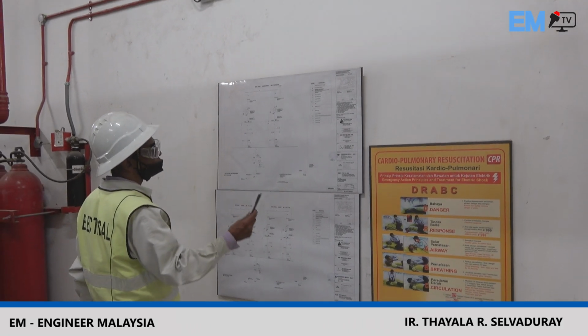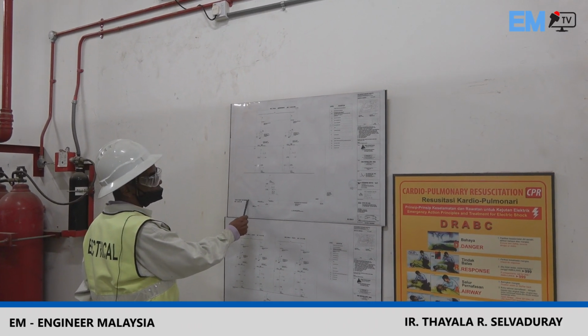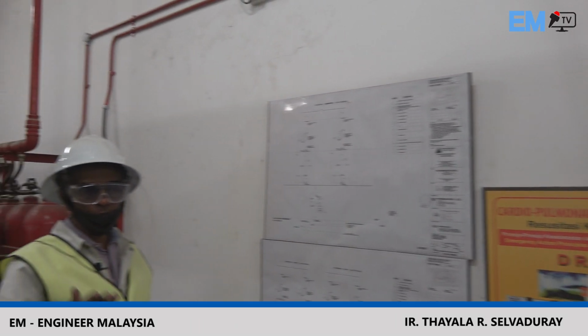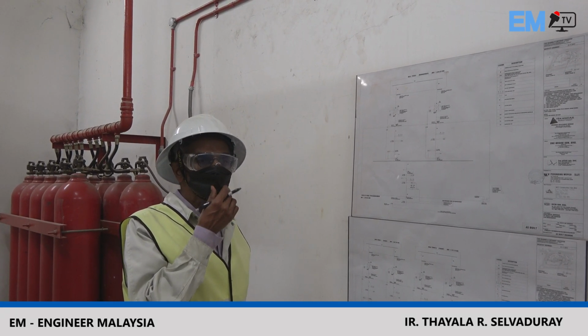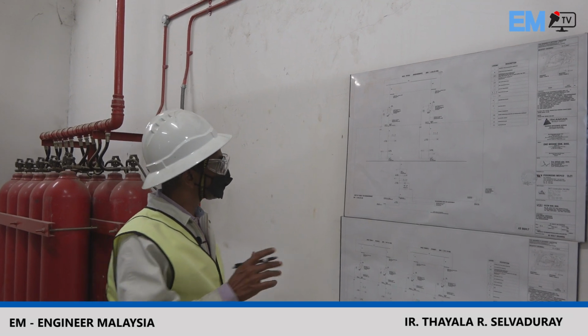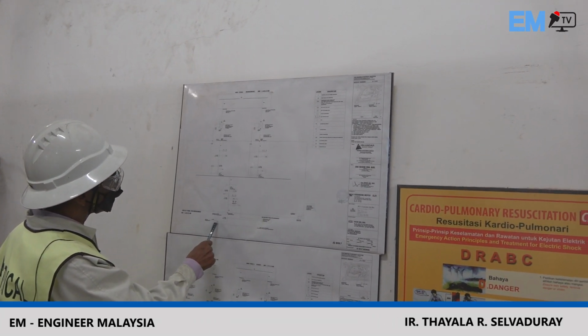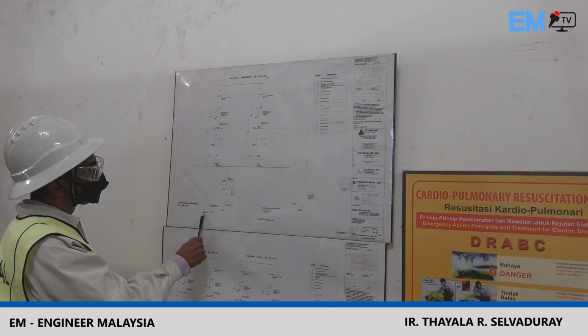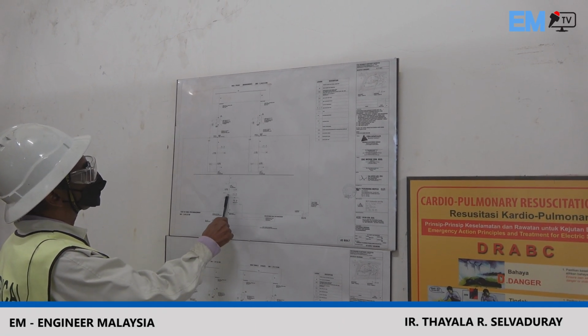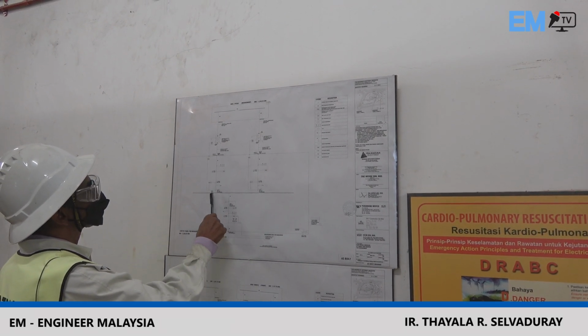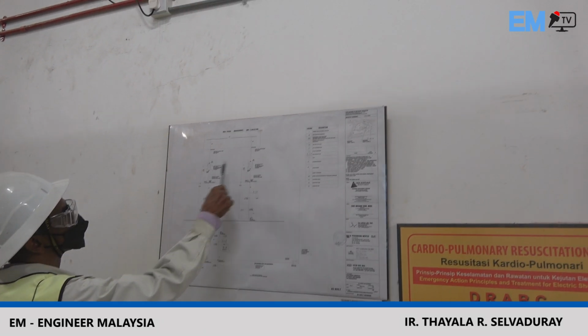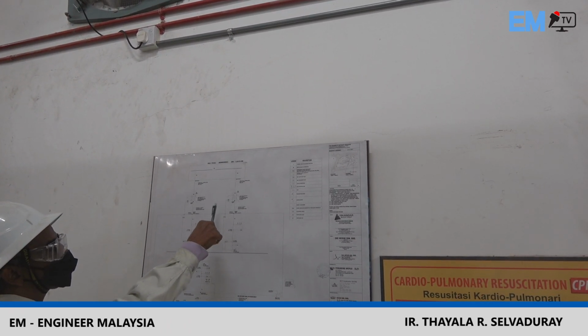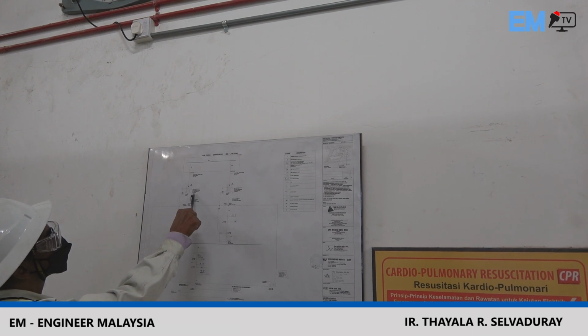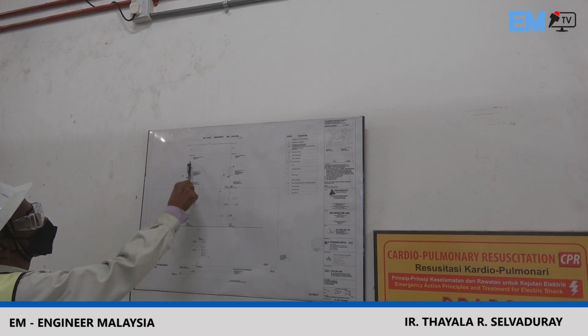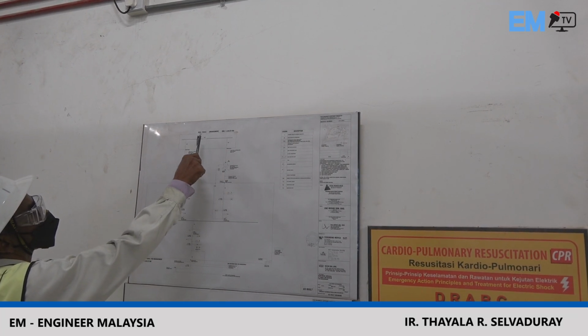Okay, what you see here, let me do step by step. This is the management. Management takes care of the emergency systems, the swimming pool, the corridors, the lifts, the firefighting pumps, the water pump, all necessary other than tenants is taken care of by the management supply. The management supply has a 33 kV supply. You call it here the 33 kV Tenaga Nasional incoming supply. They go in, and of course all the safety circuits are here. Then they go down to 33 kV down on the bus bar to the transformers. There are 2 transformers here which you saw just now. From there they are stepped down from 33 kV to 433 volts, and they are then distributed to the distribution boards for the management controls.